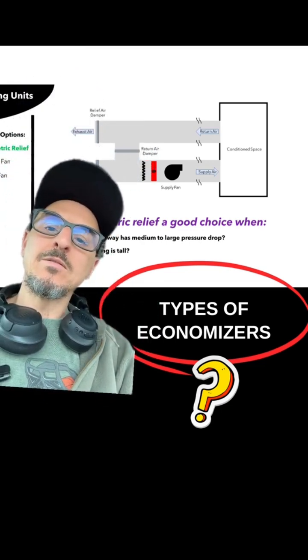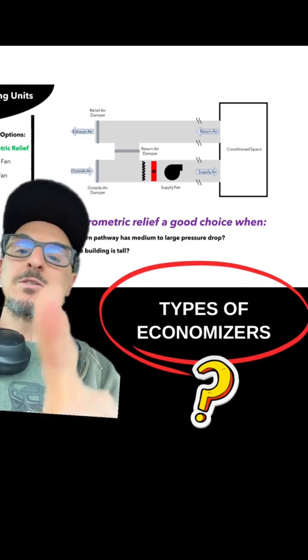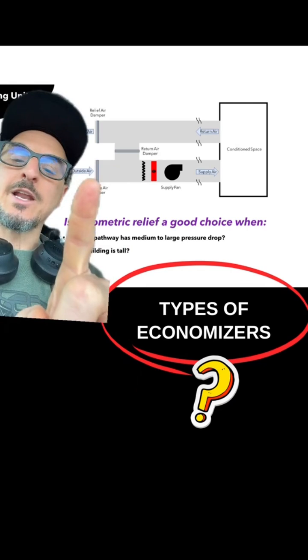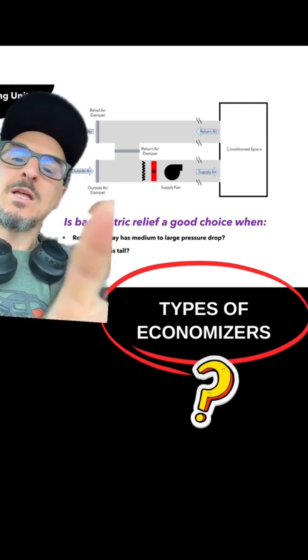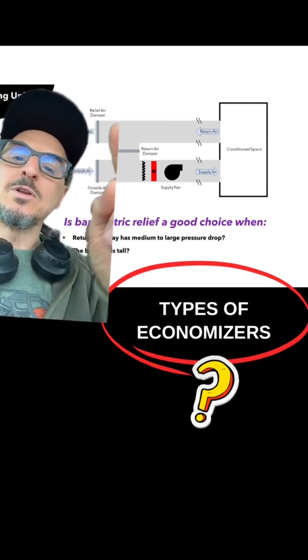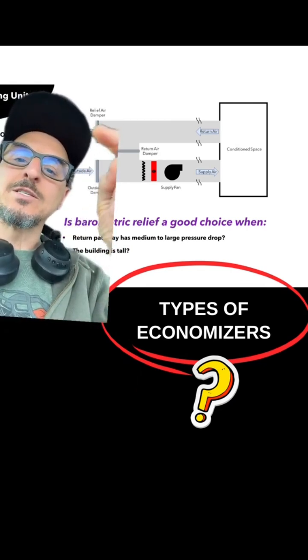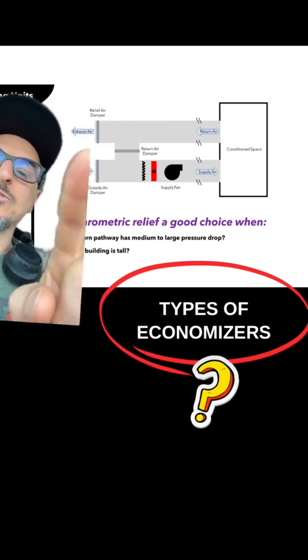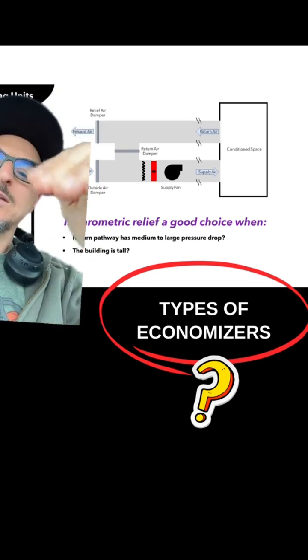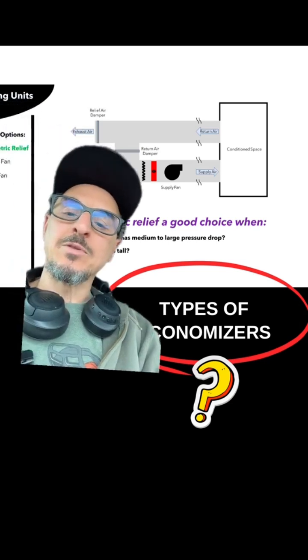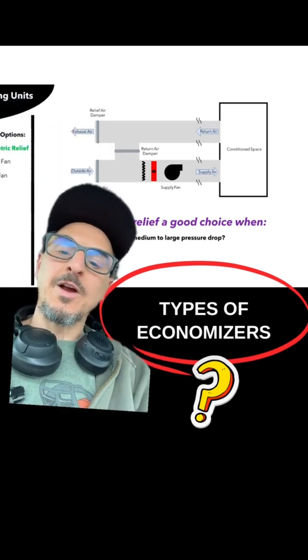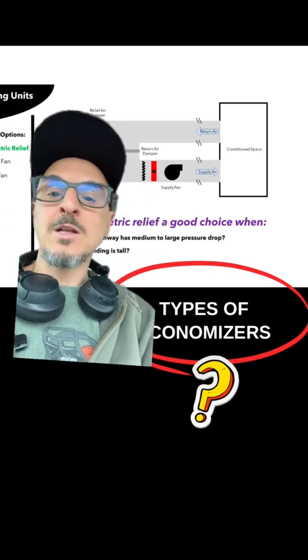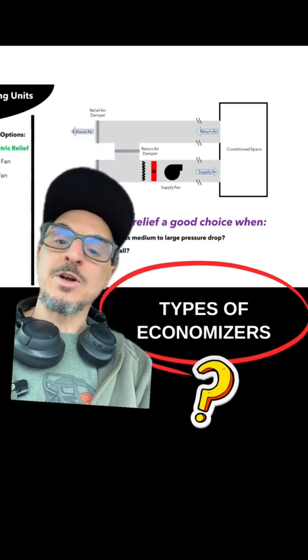The first and cheapest way is called barometric relief. The outside air gets pumped into the building, blowing it up like a balloon and pressurizing it. There's a weighted damper on the exhaust, and at a certain pressure, that damper will open and relieve the building pressure. This is very economical and works okay if you have very short duct runs and low return static pressure.